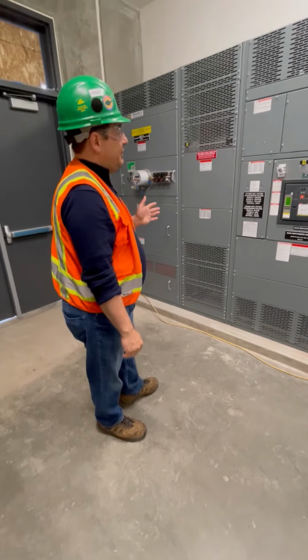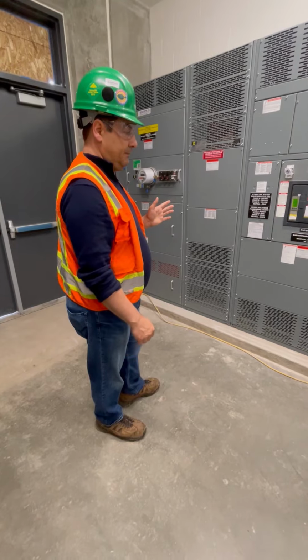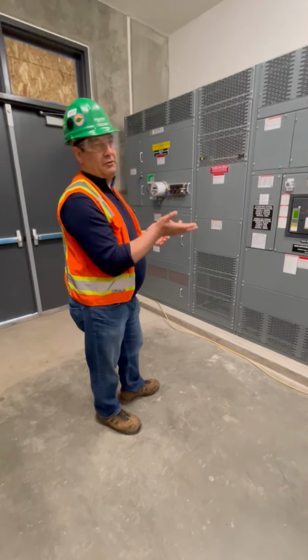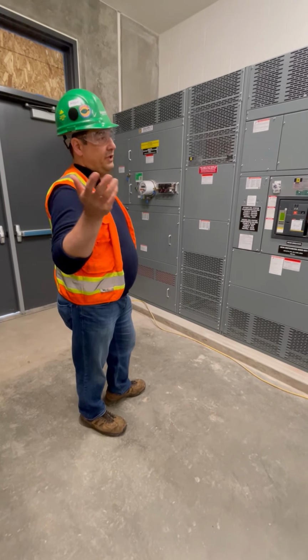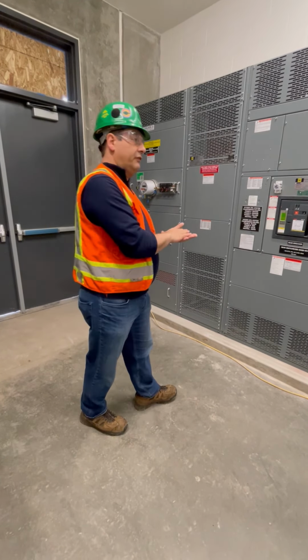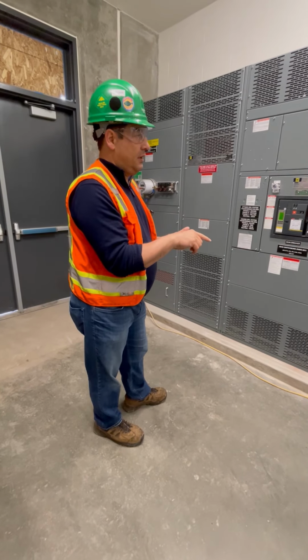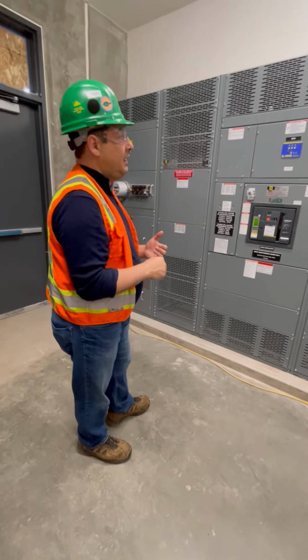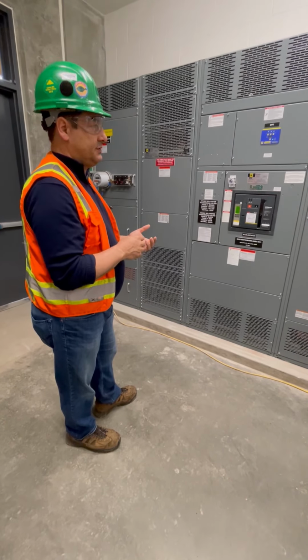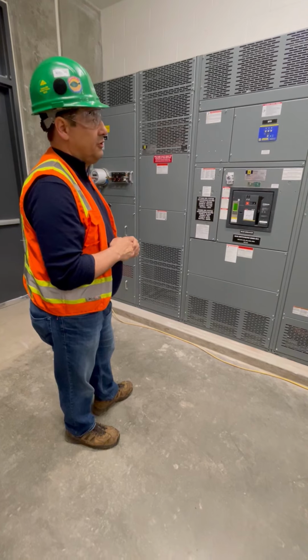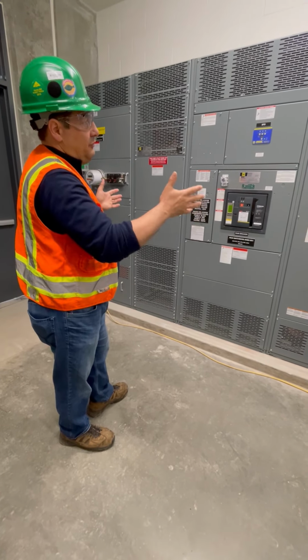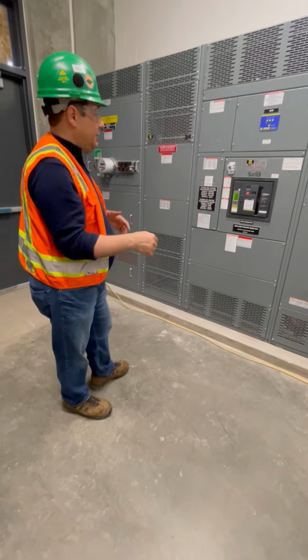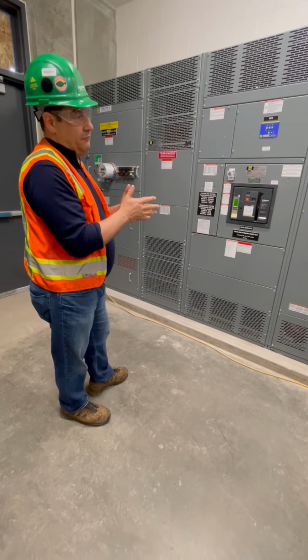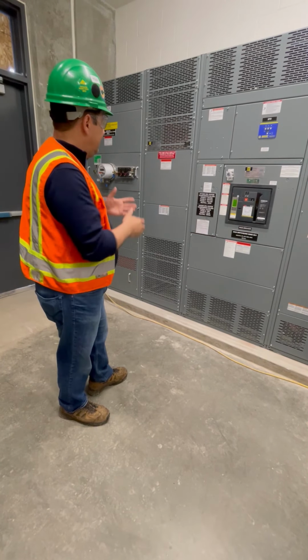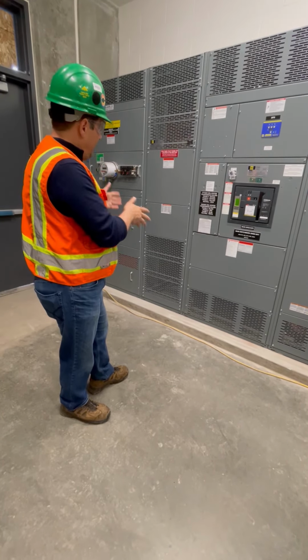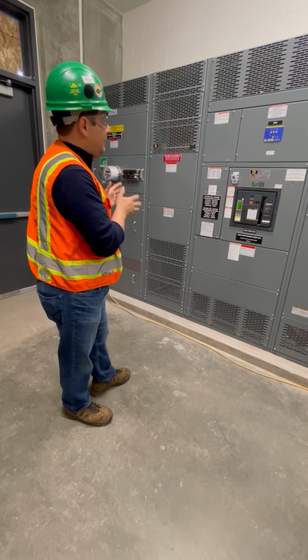A lot of customers operate these switchboards in very heavy commercial industrial facilities where there's a lot of debris going in, right? You could have cement blowing in there, or all kinds of things, which is very conductive. If it gets on the insulators, over time you can create tracking and short phase-to-phase. I've seen a lot of those switchboards, and it's scary, but they've been operating for a long time under those conditions. Now, again, to have a well-maintained switchboard, once a year you can develop your own maintenance program, and decide the frequency of you going in and maintaining it. But again, we maintain it once a year. You go in, you inspect it, you clean it, you torque it, and you test it.